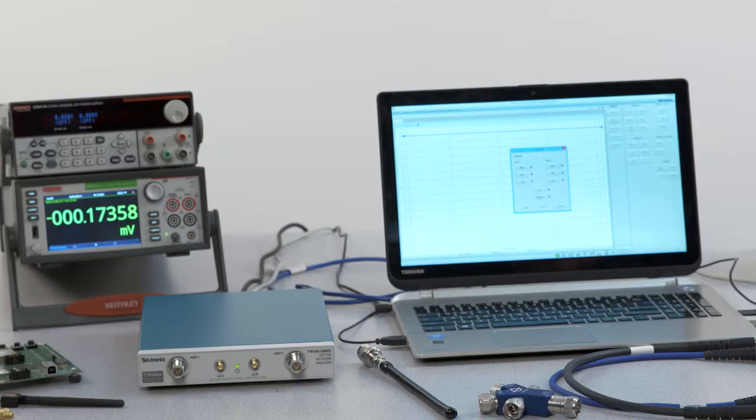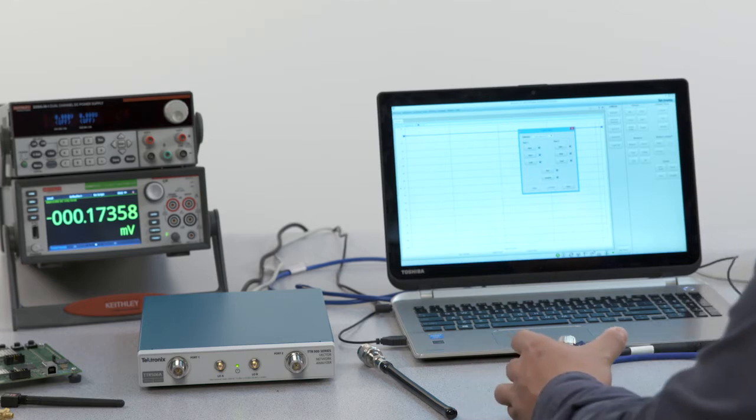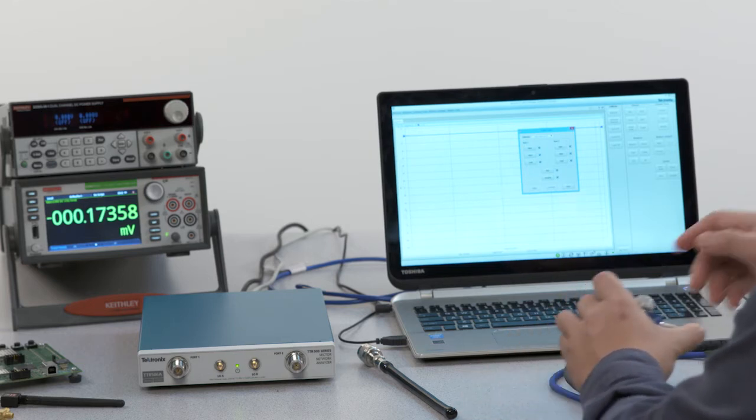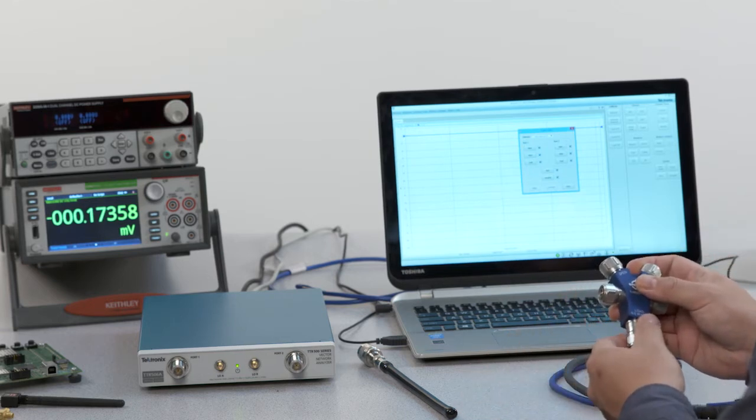Now from here click the calibrate button, and depending on the type of calibration that you'd like to do, if you want to do a single one port cal you would click on one port SOL. In our case we're going to do a two port cal or a two port SOLT cal. So we click on that and this little sub menu pops up.